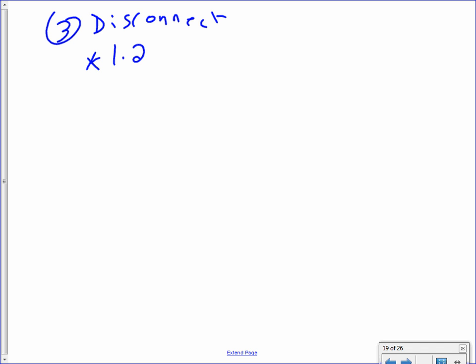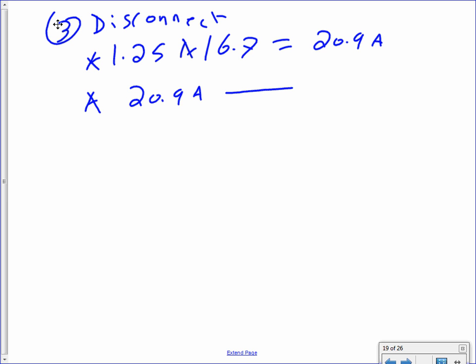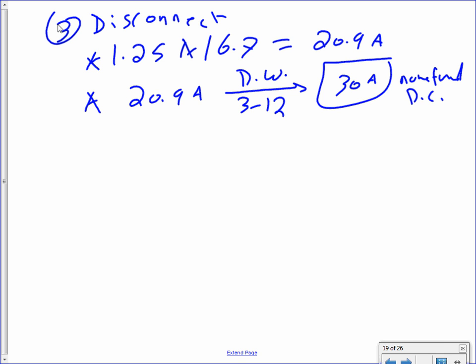Disconnect, guys, I take 1.25. I need somebody to do the math for me because I did not do the math for this. 1.25 times 16.7. We did this math. 20.9 amps. And then you take the 20.9 amps to table 3-12. We will come up with a 30 amp non-fused disconnect. 30 amp non-fused disconnect. That's my disconnect.